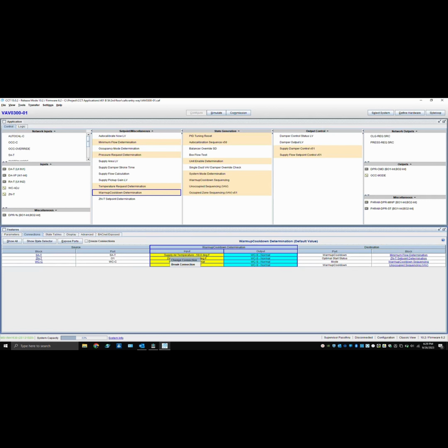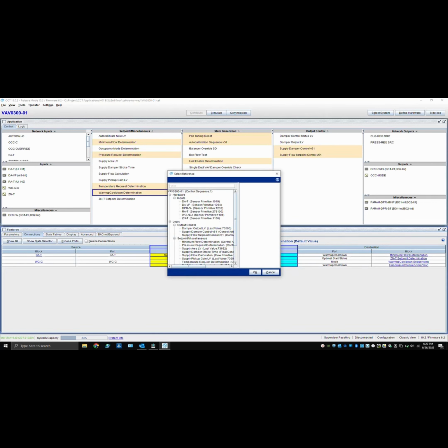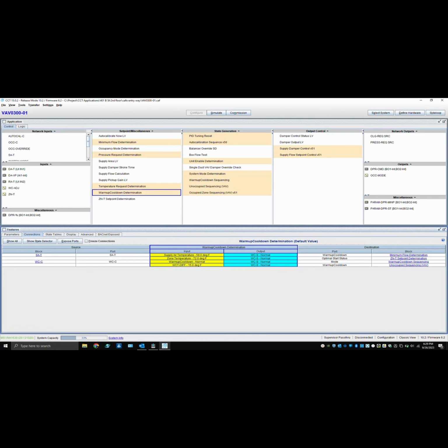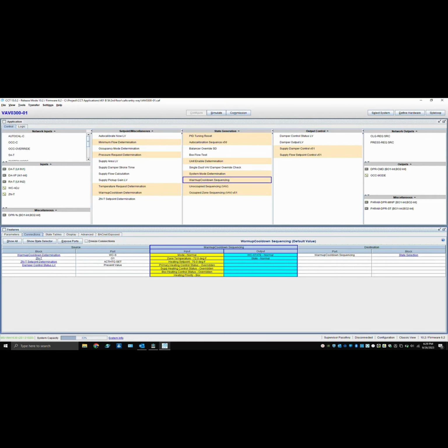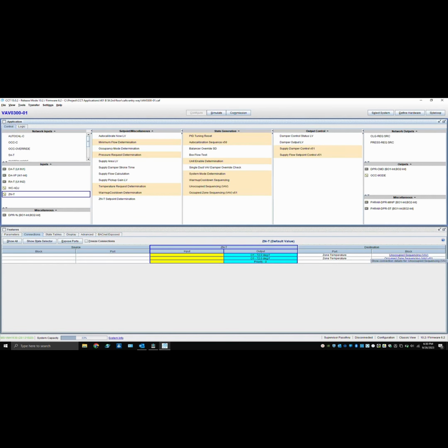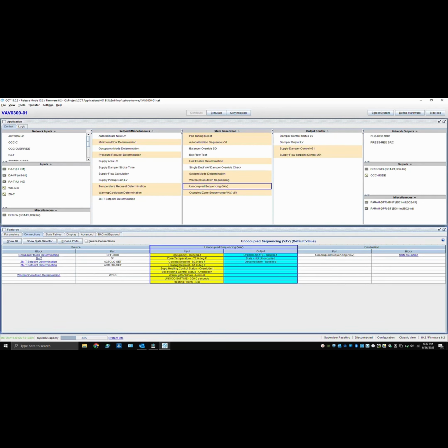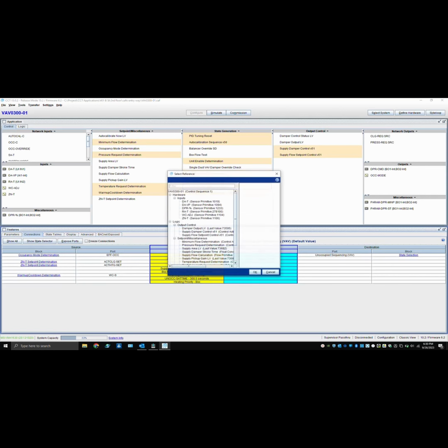But if you click on ZN-T and then click the connections tab at the bottom, you'll see on the right-hand side where it says block right now. If you click those, you can break those connections and then change them to return air temperature. And I'm just going to do this for a couple more. Basically, all I'm doing is adding a return air sensor and then telling all the programming to look at the return air sensor instead of the zone temperature sensor.